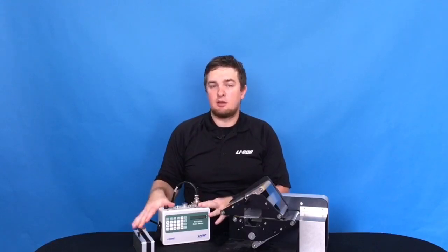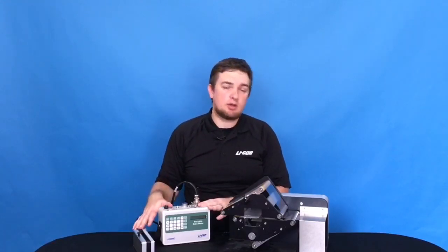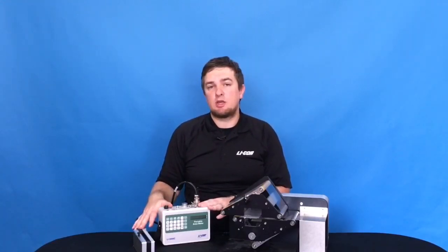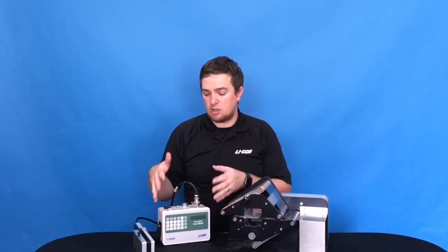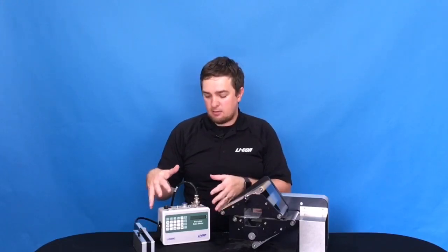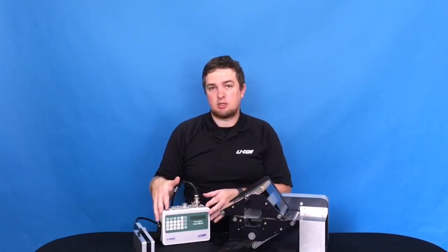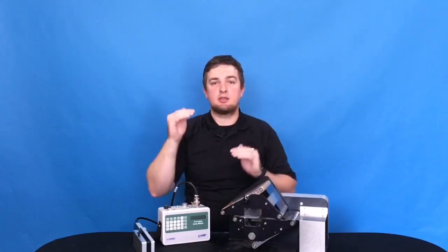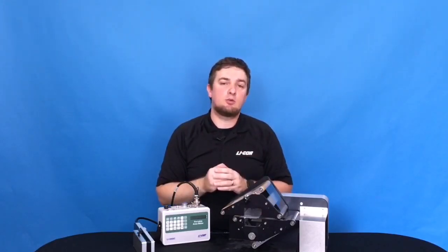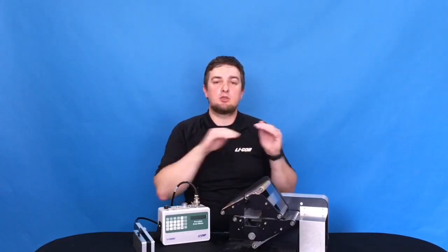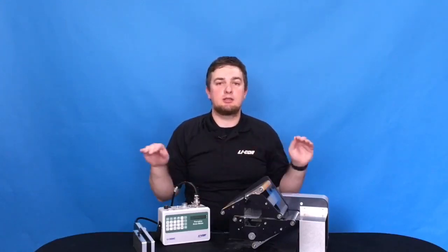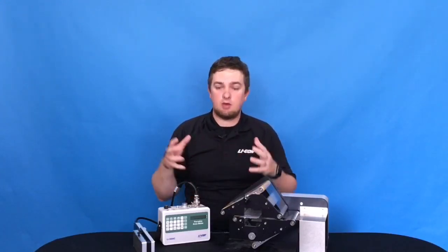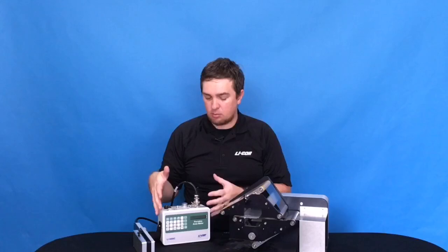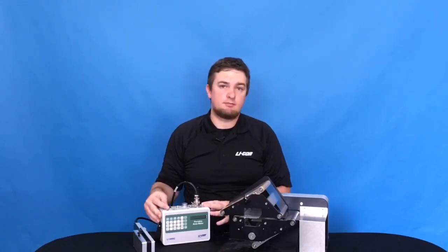There's also a way to calibrate the instrument. The instrument should not need frequent calibration, but there is a way to do it on the instrument. Basically, you would start the calibration and it adjusts the intensity of each of the 128 LEDs so that they are all of uniform brightness. So I'll show you how to calibrate the console.